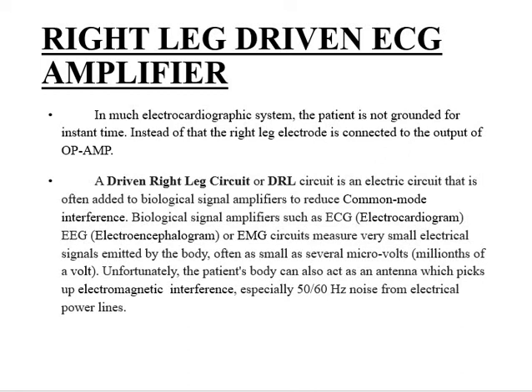If that type of grounding is taken, then the readings will not be proper. The reason is, even though there is noise, that noise might be actuated, or that signal may not be reflected in the measuring or display system. Even in some conditions, it may be eliminated as noise. So we should not take risk with that type of reading. What we have to do is take that portion — very low frequencies and amplitudes — also into consideration.